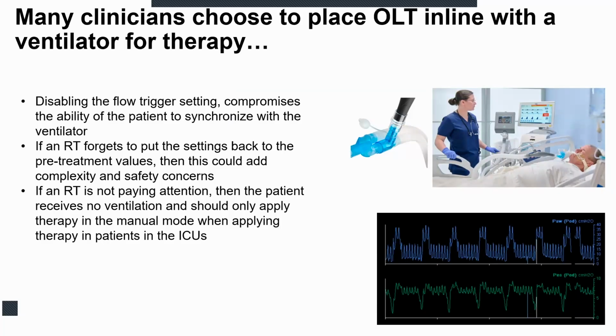You have to turn the flow trigger off. That's going to limit the ability of the patient to synchronize with the ventilator. Depending on the mode they're using, the RT almost always has to go into pressure control, right? You have to use pressure control. And I think each ventilator behaves a little differently because they have different flow control valves and different expiratory valves. If an RT forgets to put the settings back to the pre-treatment values, this could add to patient complexity, deterioration, and safety concerns.